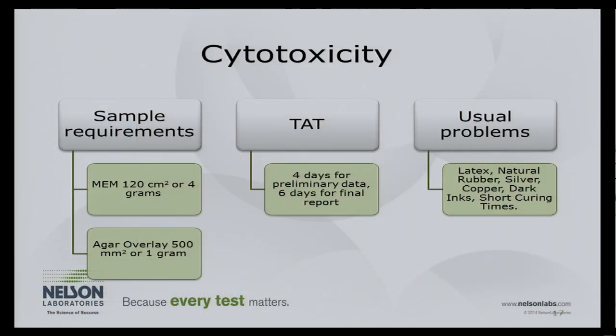The cytotoxicity test is the quickest, least expensive, and most sensitive biocompatibility test we have. At Nelson Labs, over 13 years of data, 93% of the time if you're going to fail a biocompatibility test, it's going to be cytotoxicity. That doesn't mean you'll fail 93% of the time, but when failures occur, cytotox is usually where they show up. This makes it a great screening test — if you're comparing materials or want confidence before animal testing, cytotox is a smart first step.